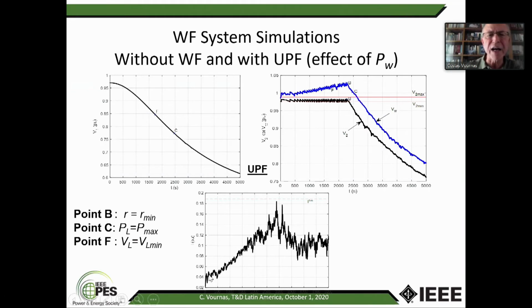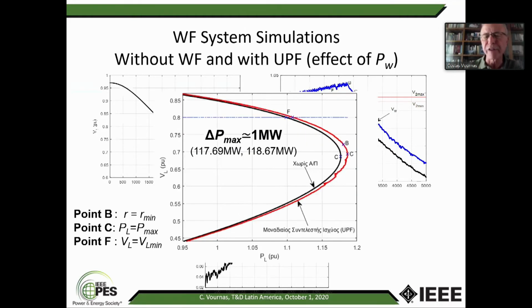This is the current drawn, to show you that in this case you never reach the current limit on the converter. And here's the comparison I mentioned. Without the wind farm and with the wind farm at unity power factor, you have a gain, but a very small one, of 1 megawatt in the maximum power transfer.